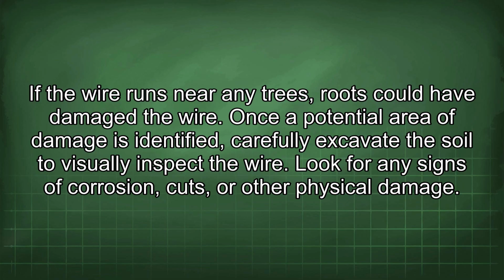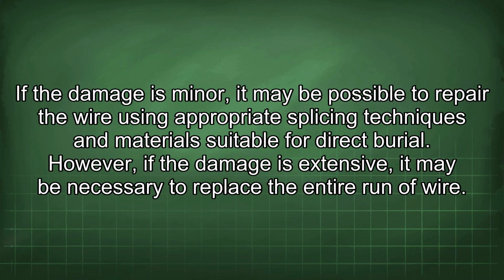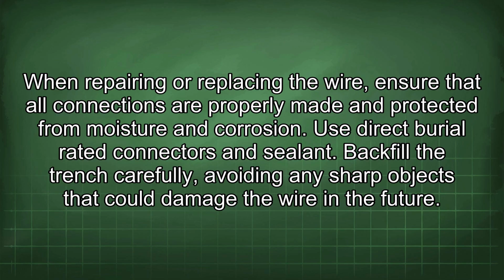Once a potential area of damage is identified, carefully excavate the soil to visually inspect the wire. Look for any signs of corrosion, cuts, or other physical damage. If the damage is minor, it may be possible to repair the wire using appropriate splicing techniques and materials suitable for direct burial. However, if the damage is extensive, it may be necessary to replace the entire run of wire. When repairing or replacing the wire, ensure that all connections are properly made and protected from moisture and corrosion. Use direct burial rated connectors and sealant.